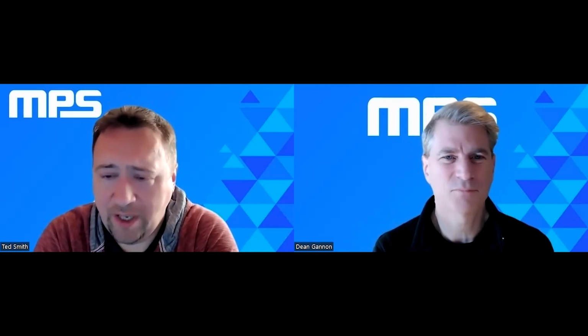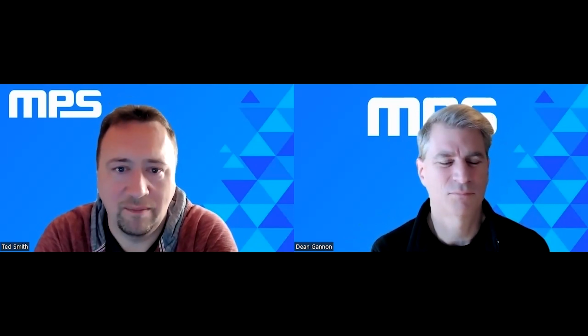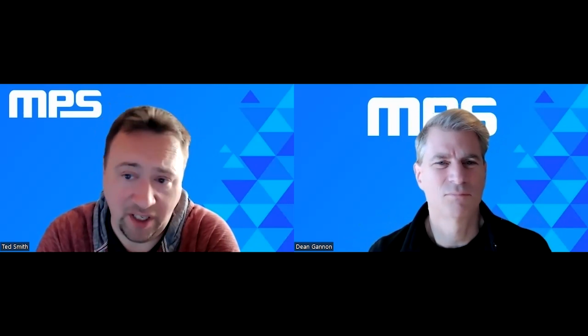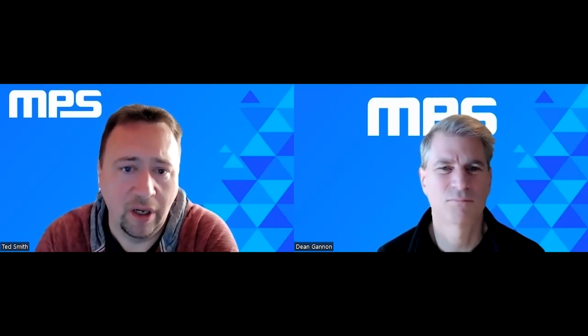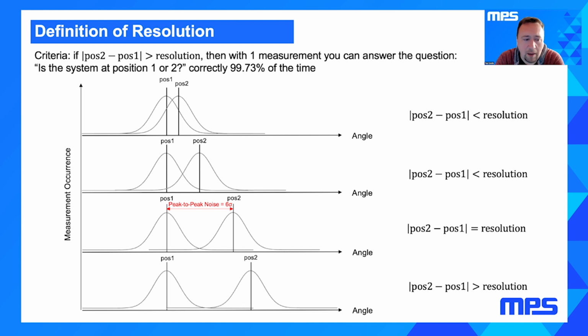Yeah, resolution on the surface seems like a pretty simple, straightforward thing. You have a part, for instance, all of our parts, we have a 16-bit word that we output. So it could be easy to say, well, we got 16 bits of resolution. But that's simply not the case for all of our sensors. In fact, we have some sensors that are 8-bit sensors. That means that 8 of those 16 bits, the 8 LSBs, are just noise. You get a free random number generator with them. It would be disingenuous of me to call those 16-bit resolution encoders, because they're not. They have a 16-bit word, but only 8 real bits of information.